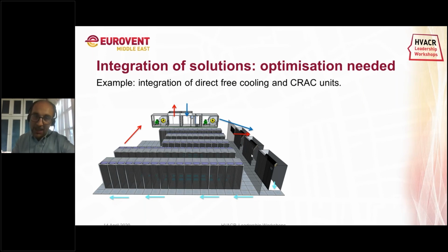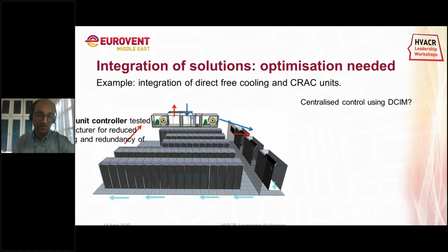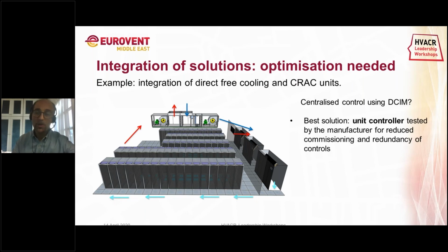So existing CRAC units combined with air handlers for free cooling, direct and indirect type, but also different areas with different temperatures or UPS or battery areas cooling. They might use different technologies. And as we are using different technologies, there is a need of coordination of all these different technologies. So very often, and this is what is popular, it might be a legitimate question: shall we have all these components then being directed by the BMS, by the DCIM? Probably, and definitely this is what also was said before, each unit should be optimized, whereas there are a lot of opportunities if the unit controller can be integrated.